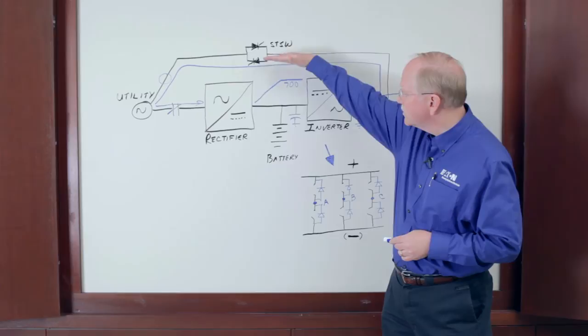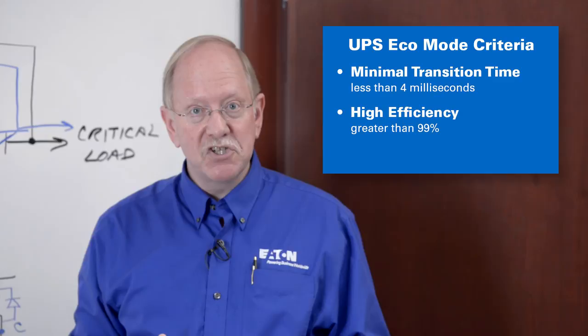So, if you're considering using eco mode on your UPS, there's three criteria that should be important. The first one is transition time. The time it takes from static switch operation to traditional double conversion should be less than four milliseconds, ideally less than two milliseconds, or two one-thousandths of a second.